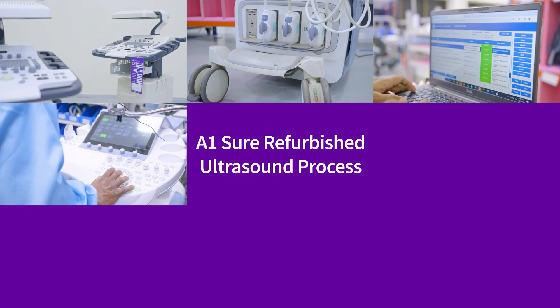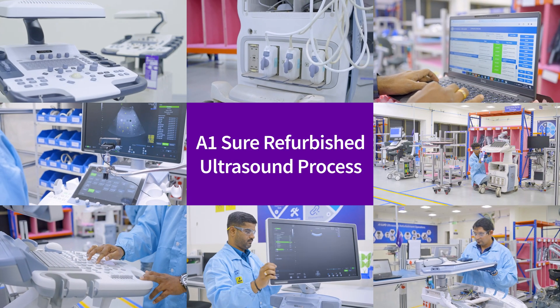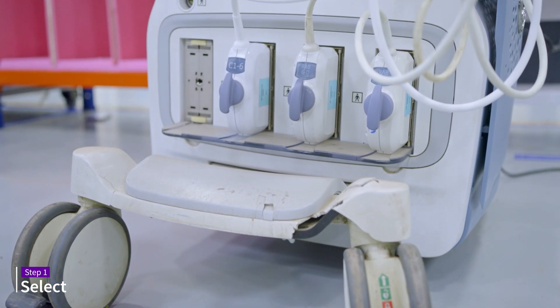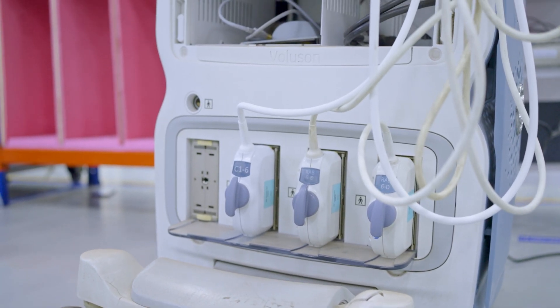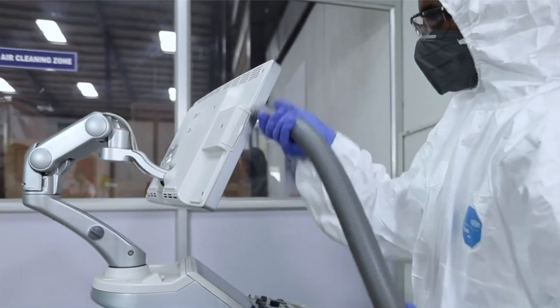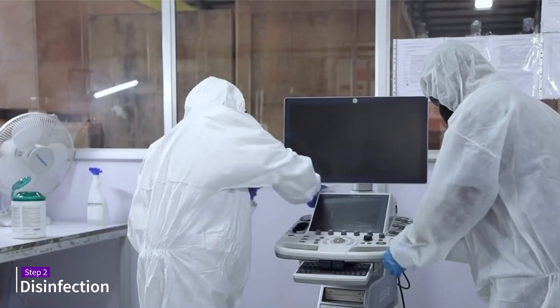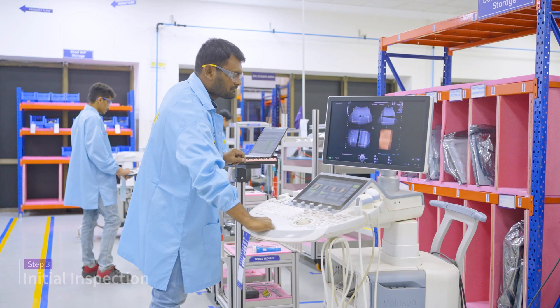Let's understand how the A1 Sure refurbished ultrasound process works. The process starts with selecting only those systems that can meet our stringent standards for refurbishment. The equipment then undergoes a certified disinfection procedure. A series of visual and functional checks are performed in the initial inspection.